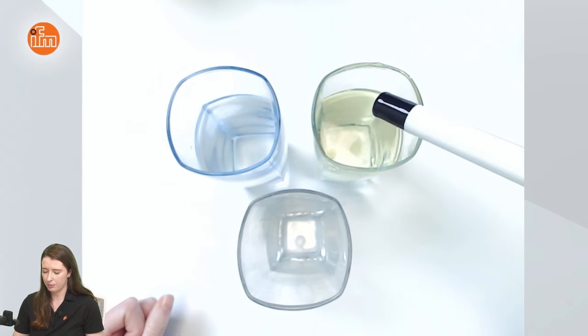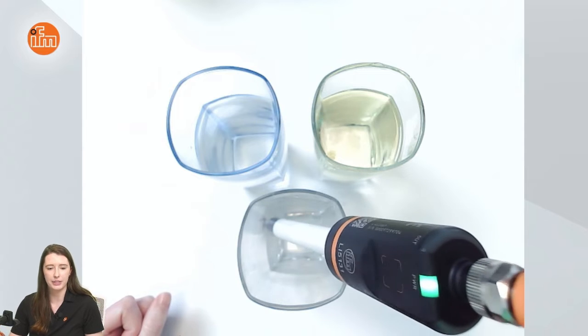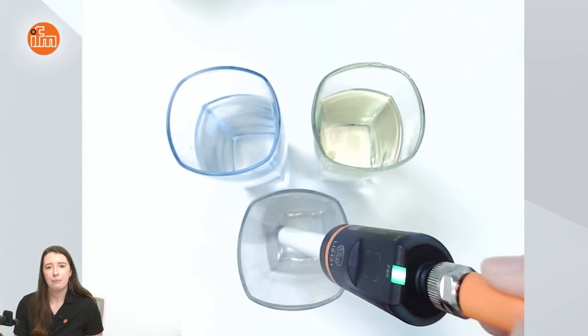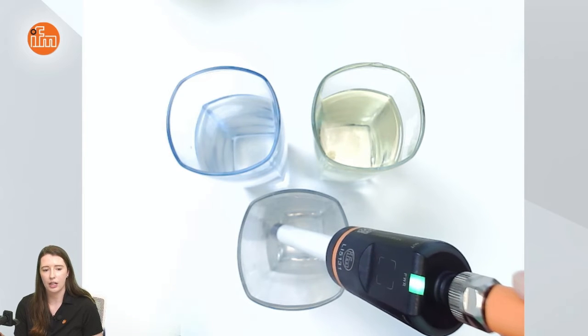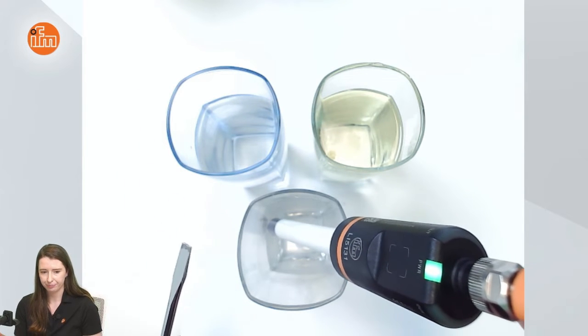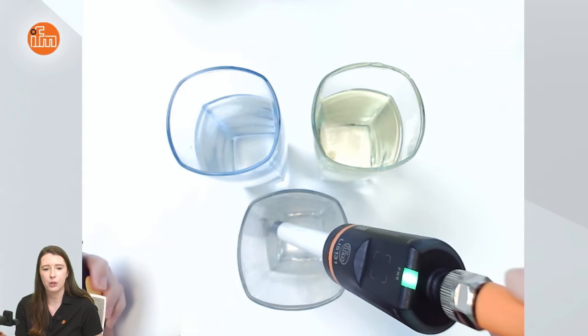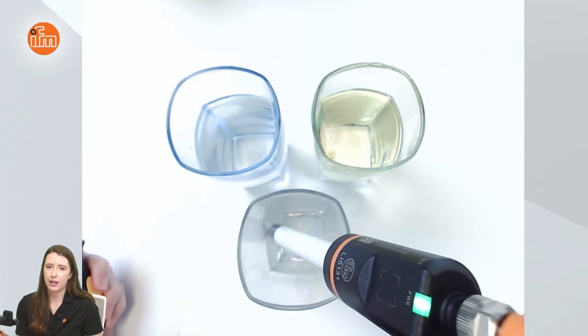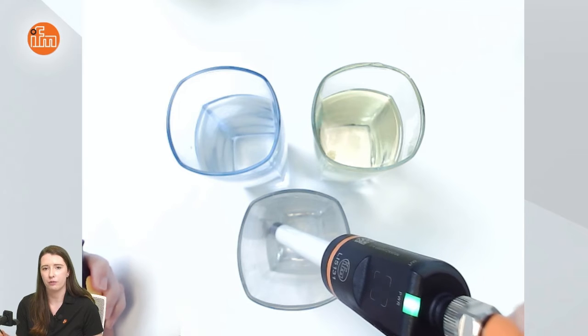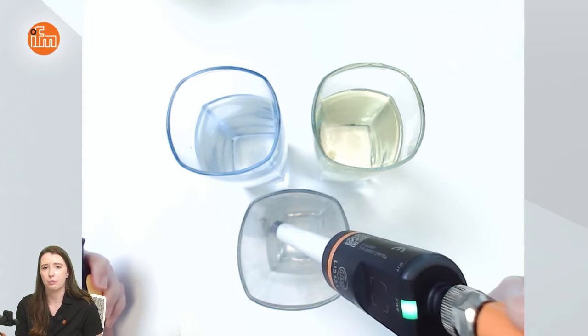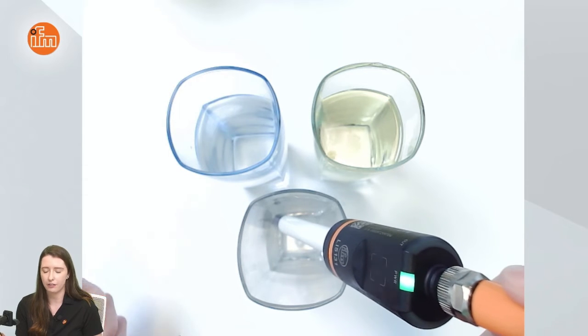So to begin I'm going to put the sensor into the empty glass to perform an empty teach. You need a metal object in order to do this so I'm going to be using a screwdriver. To begin you need to put the sensor into the programming mode and you do this by holding a metal object to the inductive teach button for at least 10 seconds and you will confirm that you are in the programming mode by the green LED flashing twice.